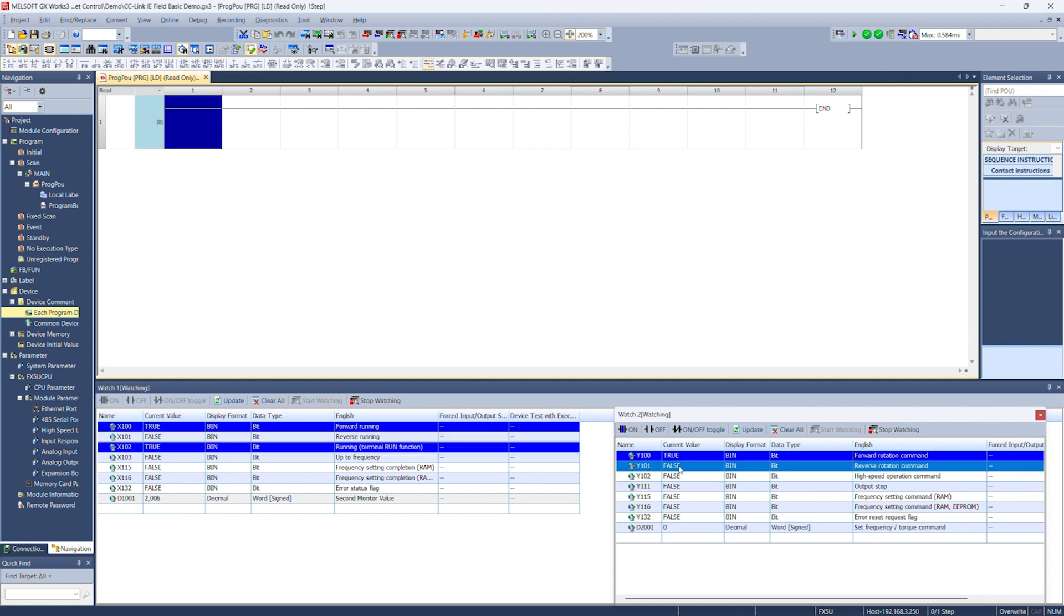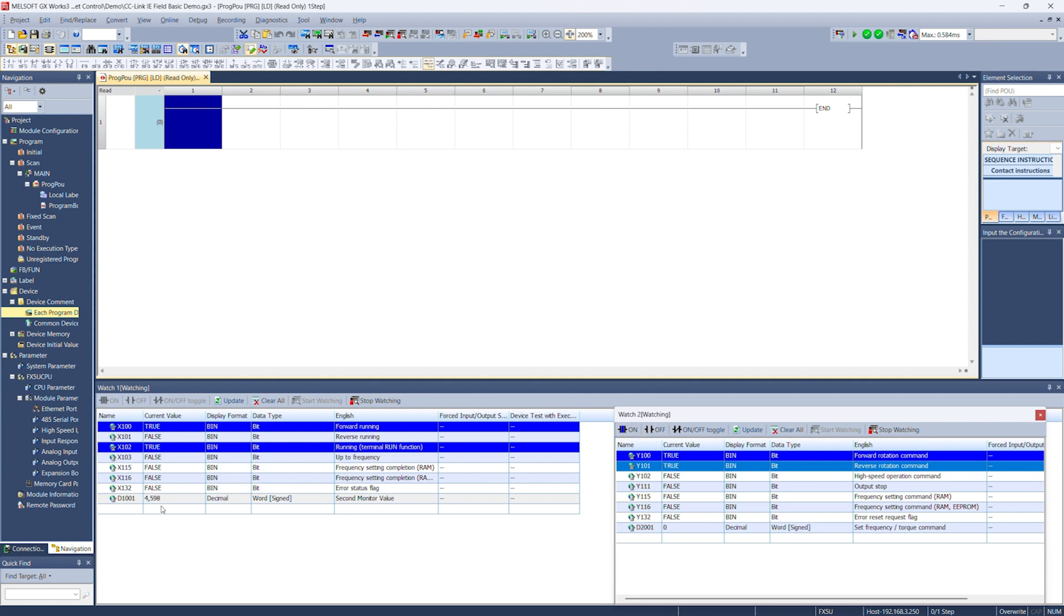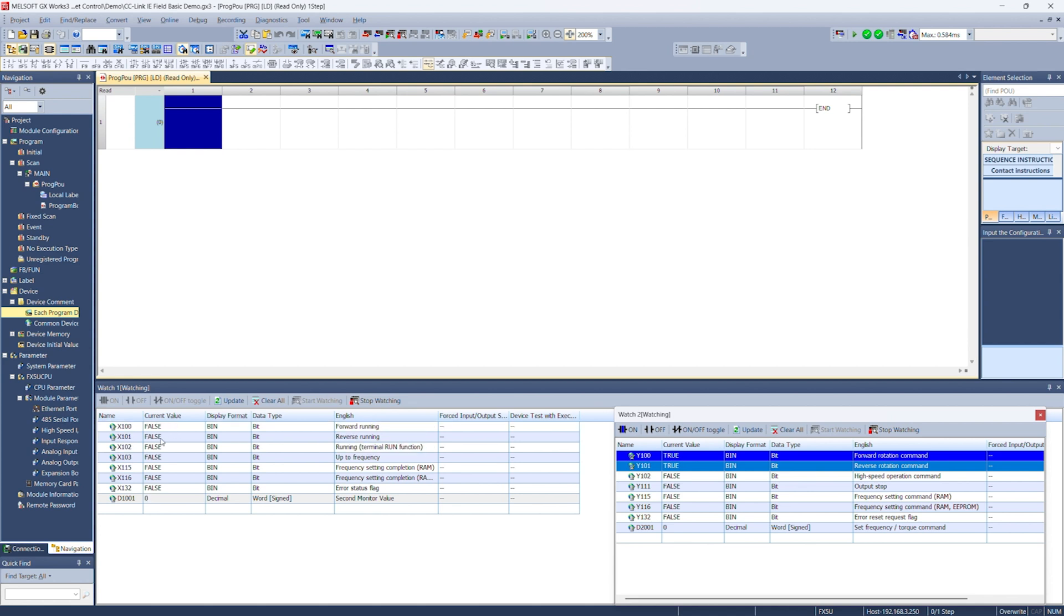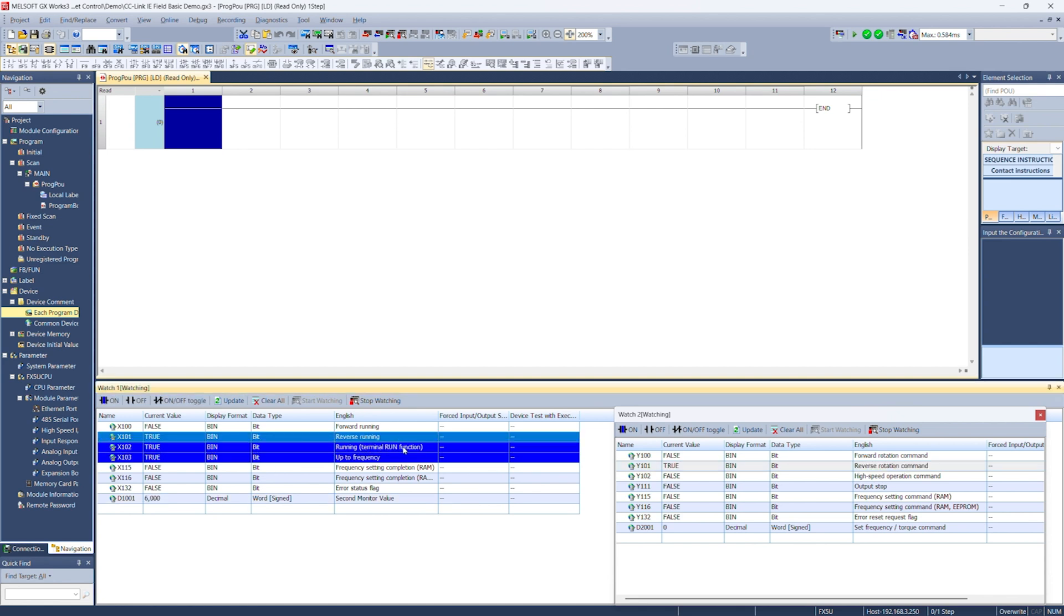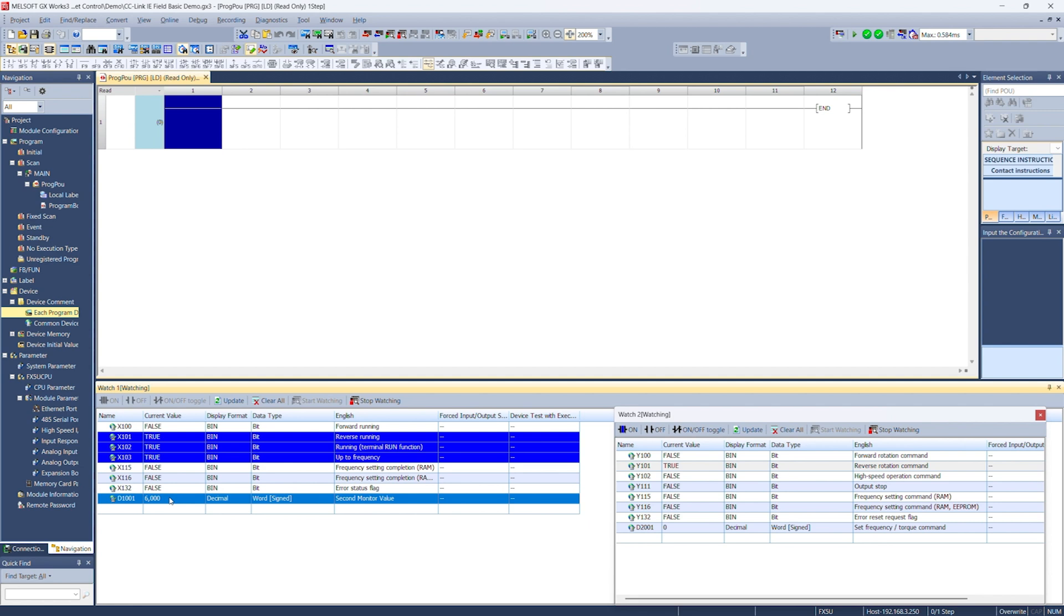What happens if we set forward and reverse at the same time? We lose speed. We're turning down to 0 and we are not running. So if you have both forward and reverse on at the same time, it is the same as having neither. We'll go ahead and turn off the forward command. So the reverse command now only is on. And we can see we're running in reverse up to frequency. We've hit our speed. Great.